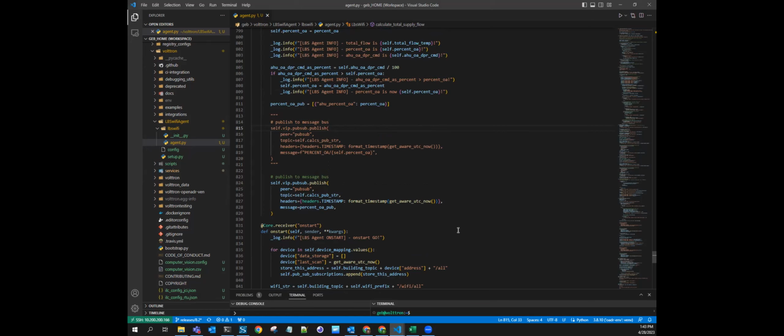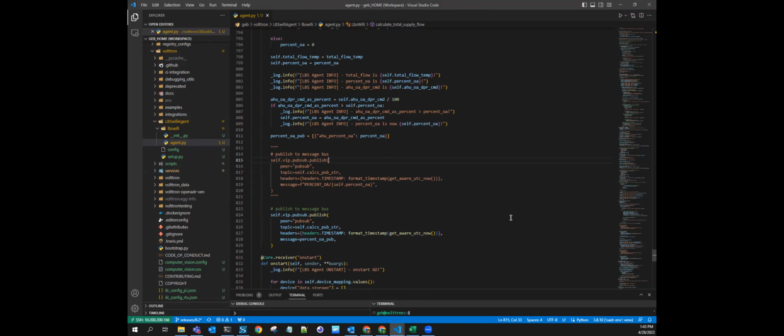Okay. So your historians pub. The historians subscribe to devices topics and they attempt to parse them, assuming that they are formatted this way. That's why it's locking up that agent. Yep. It will actually accept just one dictionary, I believe. I posted the topic syntax in the chat. Yeah, but the better convention is the list of 2 dictionaries as he's describing.